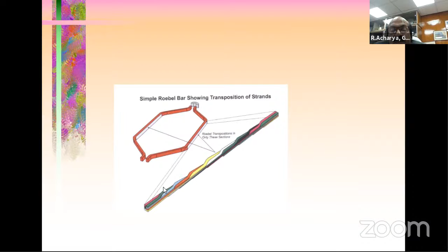I was telling you that each and every winding consists of two separate arms, and each arm in the straight part has the transposition. Each and every conductor is bent from top to bottom and bottom to top. That's what we call a 360-degree transposition. As you can see over here, a pictographic or rather schematic view of a 360 Roebel transposition of individual conductors. And there are different losses that we all know: I2R losses, eddy current losses, and circulating current losses. All these are addressed by doing a suitable transposition and choosing the number of conductors.